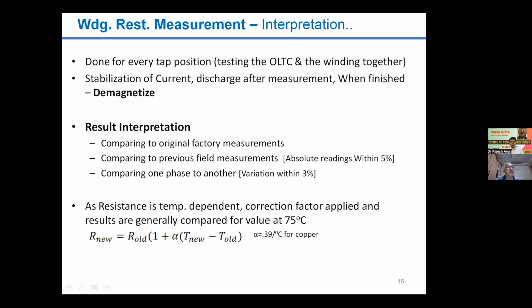Nowadays the testing kits have an arrangement that if you put the value of the ambient temperature in the kit, accordingly it will compensate for the value, and the resistance will be recorded according to the required temperature. So the formula is given, though it has been given in the last. R new means the resistance at whatever temperature you want to convert to, and R old means whatever is the measured value of the resistance.